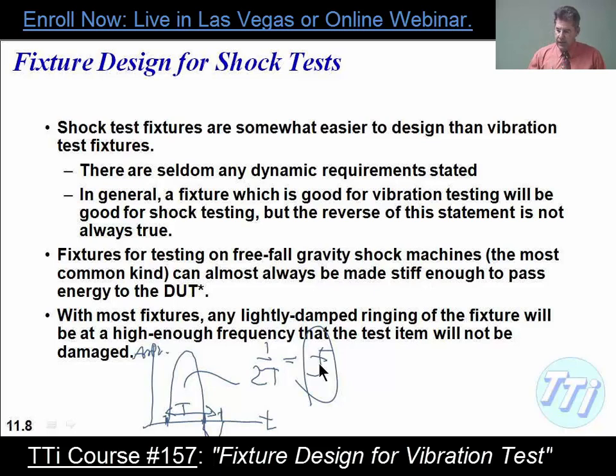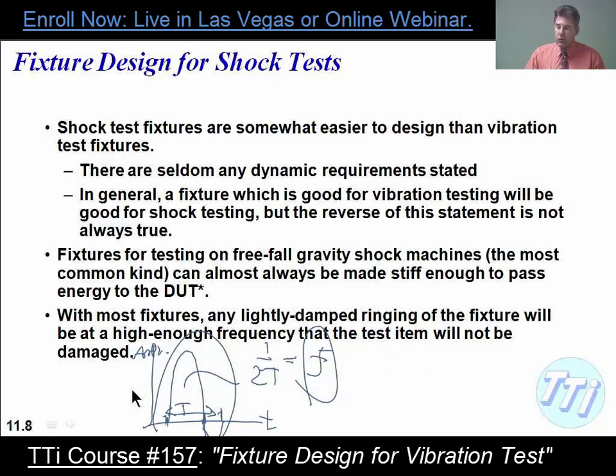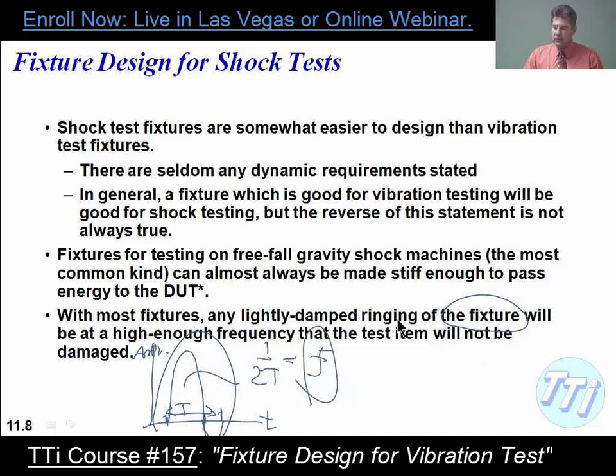As we discussed in the shock section, a structure subjected to shock responds under both forced and free vibration. Your fixture transmits this frequency well, and then it just has to support the lightly damped ringing that normally won't damage the fixture or the device. Even if your fixture rings after you hit it with that pulse, that's generally at a very high frequency, and it doesn't damage the device because the device can't generally respond to it since it's so high.